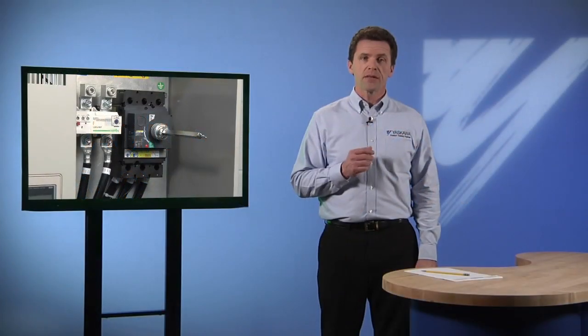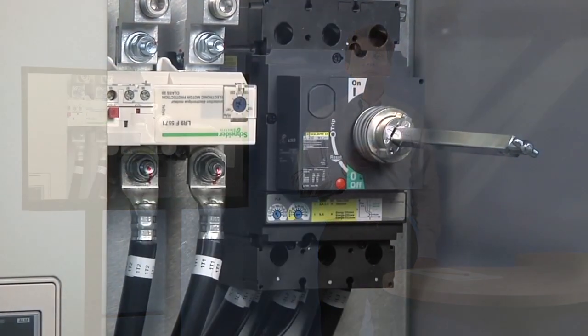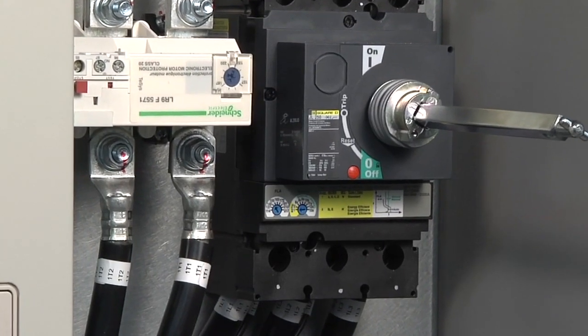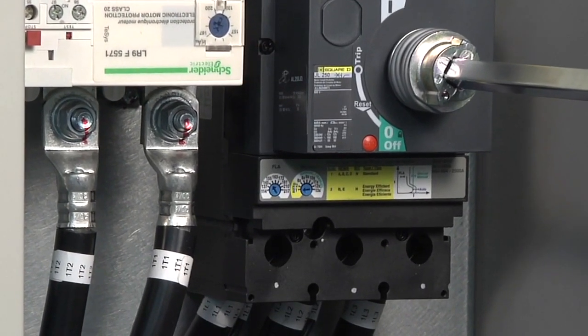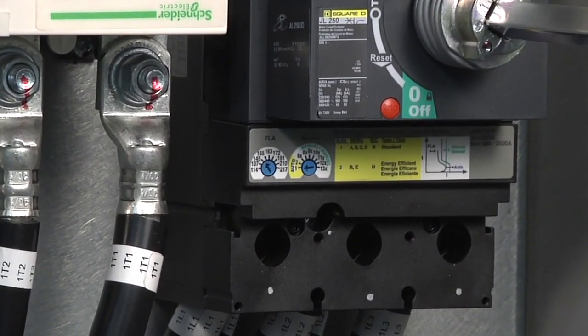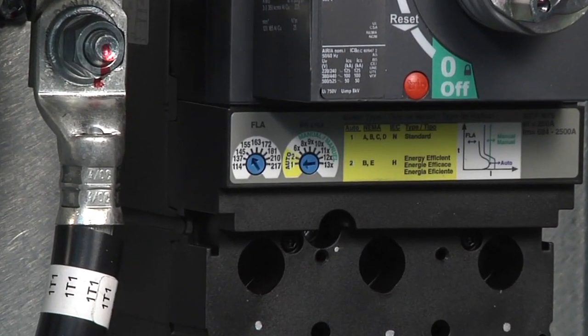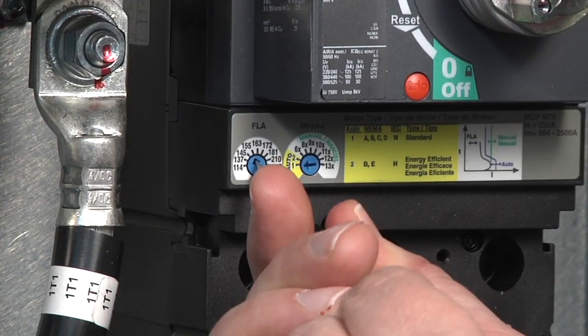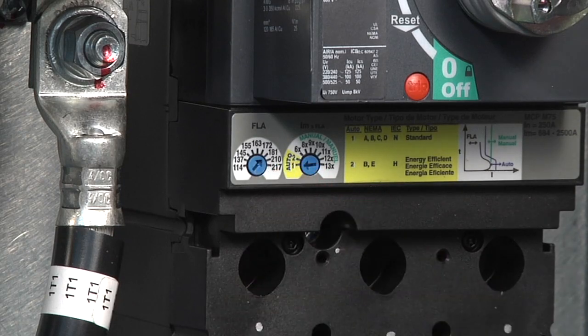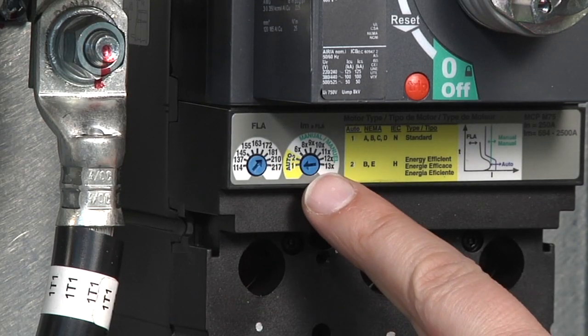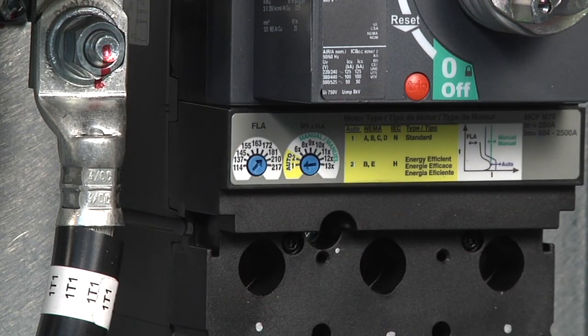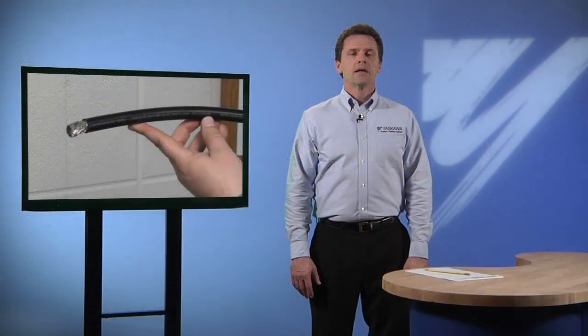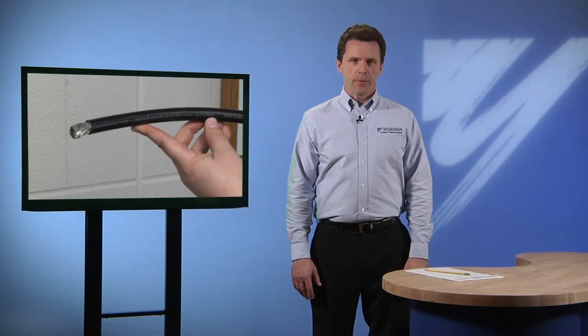The first step in setup is to adjust the circuit breaker to match the full load amp rating of the motor. And this is done by adjusting two dials on the circuit breaker with a small bladed screwdriver. Adjust the full load amp dial to match the rating of the motor. The other dial is an overload, and it should be set to Auto 1, the setting it received at the factory. Now we are ready to connect our line power.